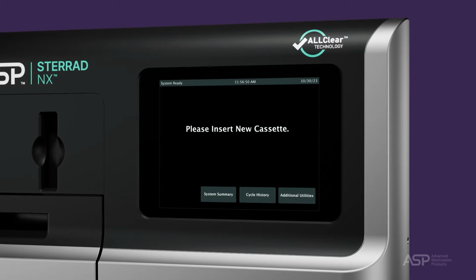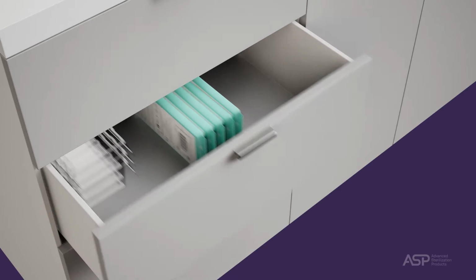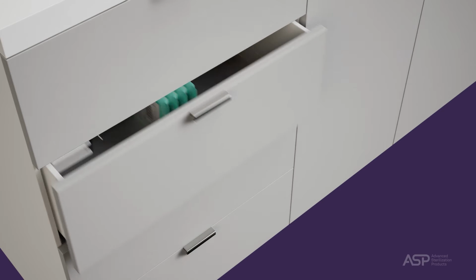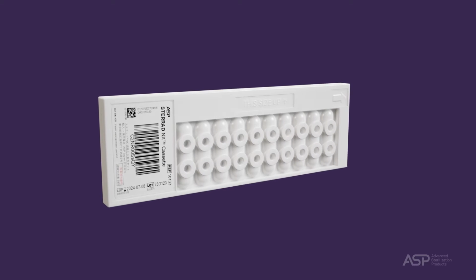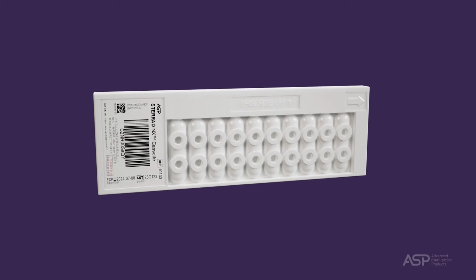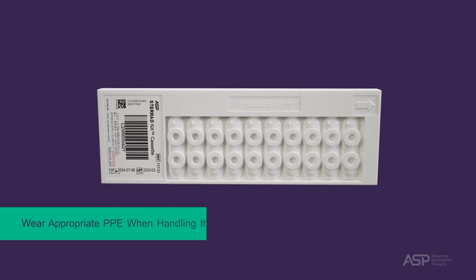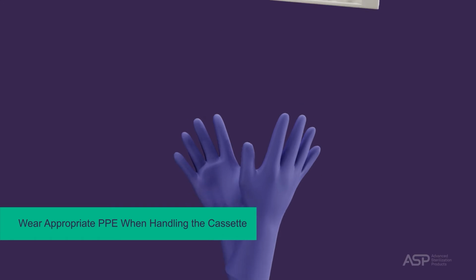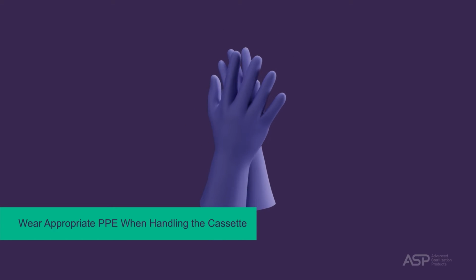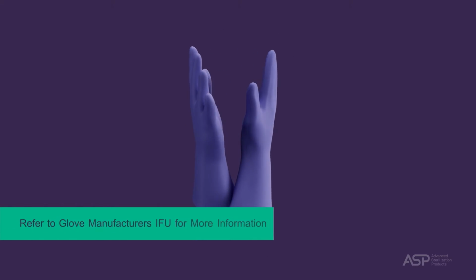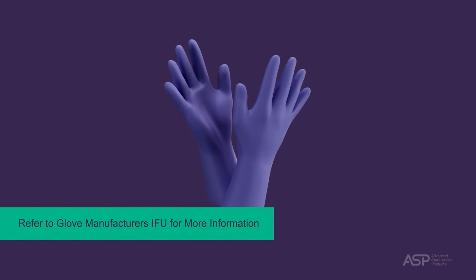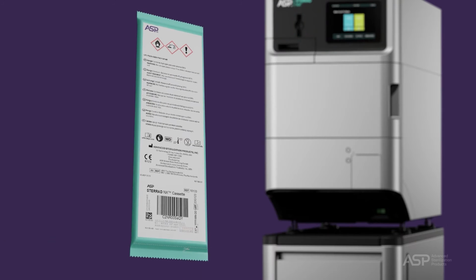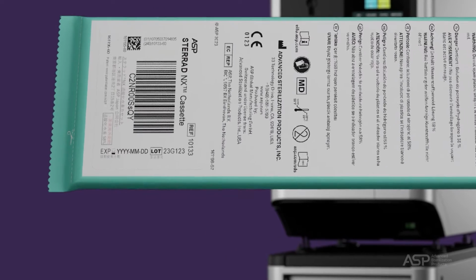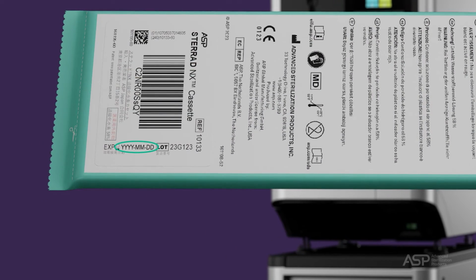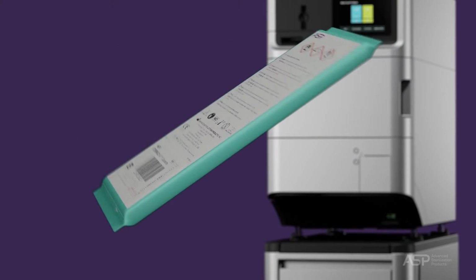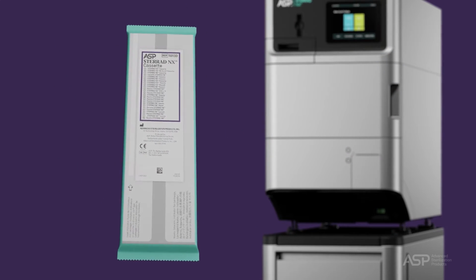The next steps should be followed to insert a new cassette. First, take a new STERRAD NX sterilizer cassette out of the shipping carton. As a precaution, when handling any part of the system or load items that have been exposed to hydrogen peroxide, please wear appropriate PPE, specifically chemical-resistant latex, PVC, vinyl or nitrile gloves. Refer to the glove manufacturer's instructions for use for more information. Look at the package carefully before opening it. Check the expiration date before using a cassette. Do not use an expired cassette. If you see droplets of moisture, do not open the package.